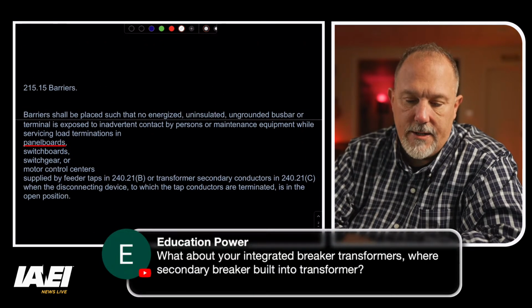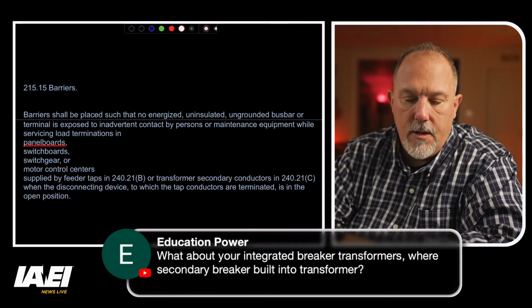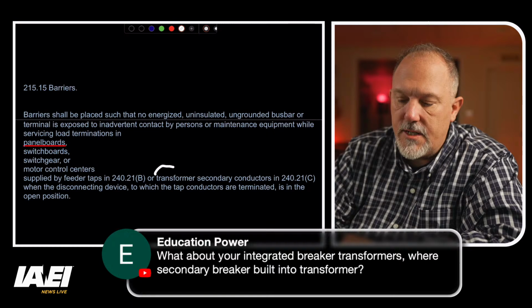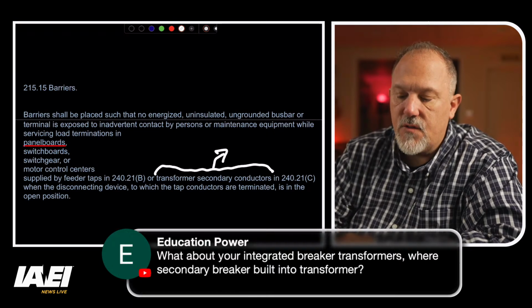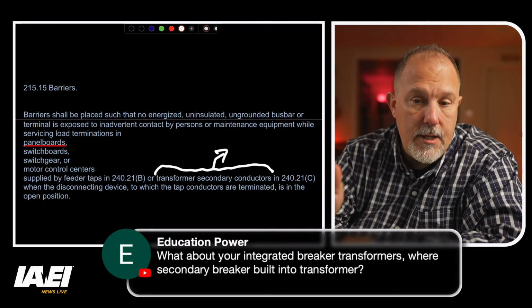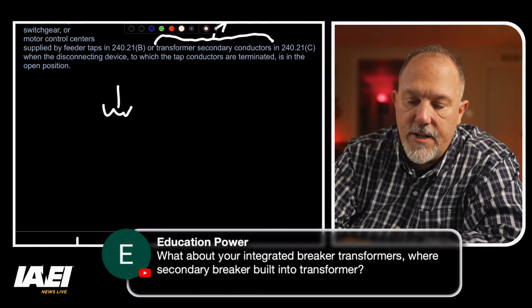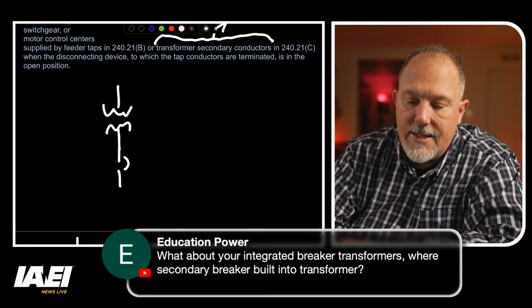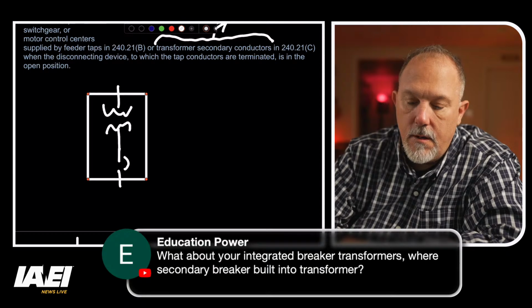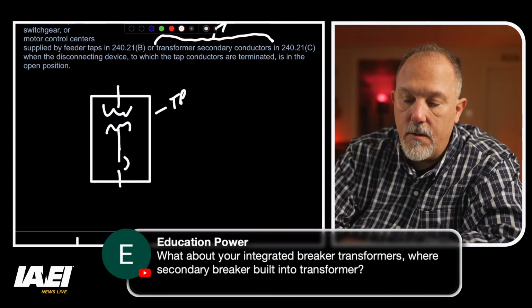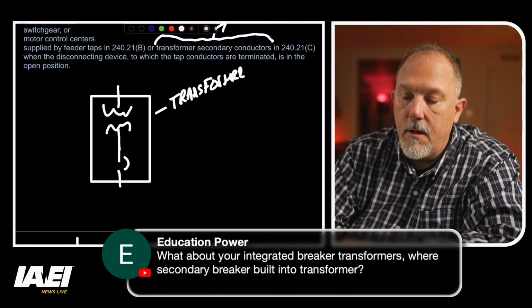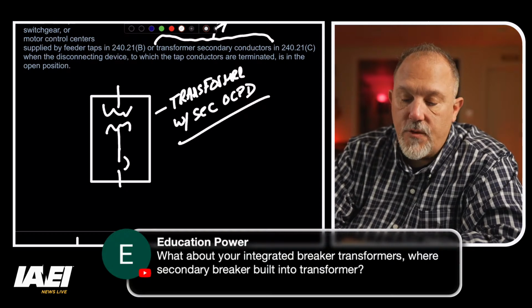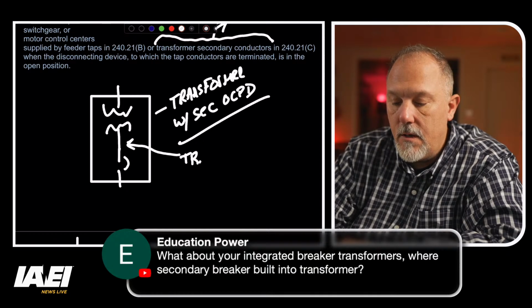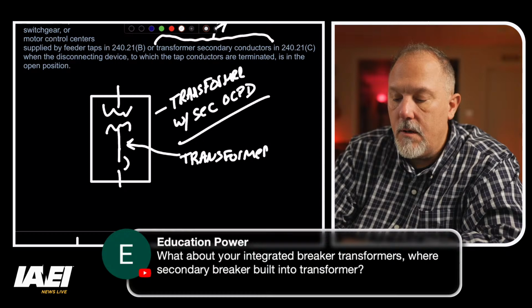So the way this code is written, barriers shall be placed in equipment supplied by feeder taps or transformer secondary conductors, right? So a transformer secondary conductor is going to be a defined term in the 2026 code. If I have a transformer and I come to a breaker, and let's say that this is all one unit, all listed as a transformer with a secondary OCPD, the transformer secondary conductor, that's the transformer secondary conductor.